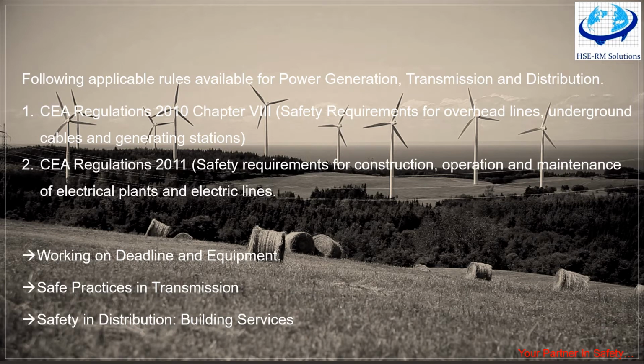After switching off the supply, before touching the line, each conductor of the line shall be tested for pressure, voltage by discharge rod. Now ensure that there is no possibility of back feed due to some emergency electrical supply such as DG set, inverters or other energy source installed in the system. All details should be specified in the permit to work, and all conductors shall be earthed. The pole on which the work is to be carried out should also be earthed.